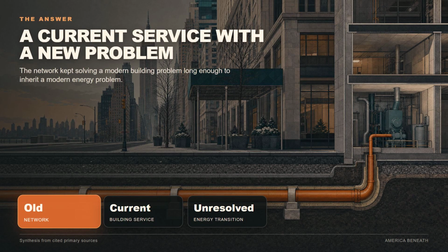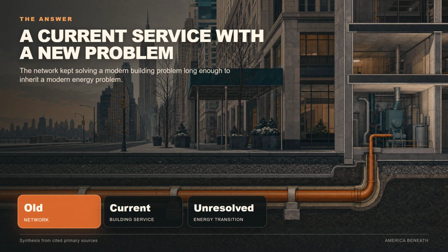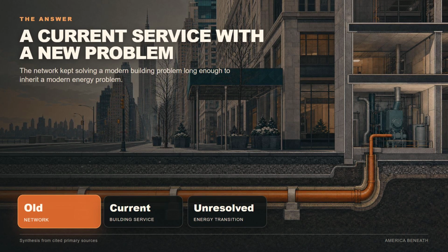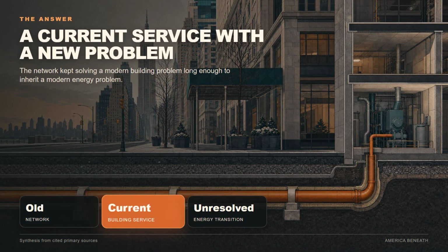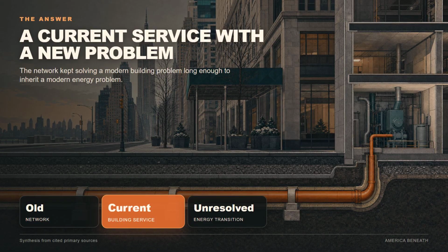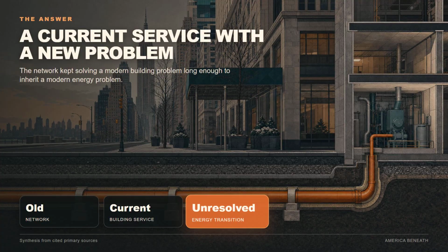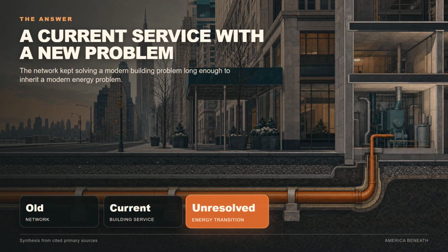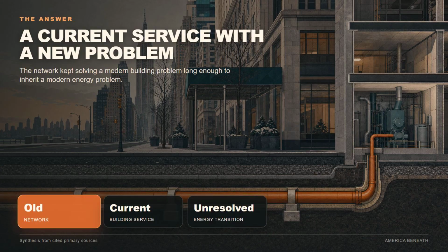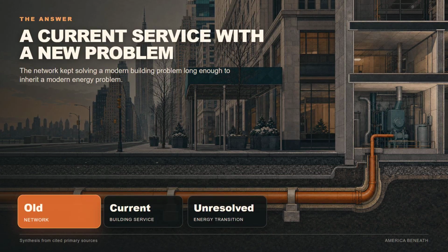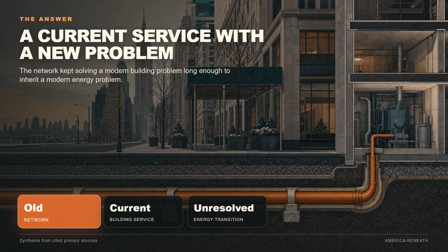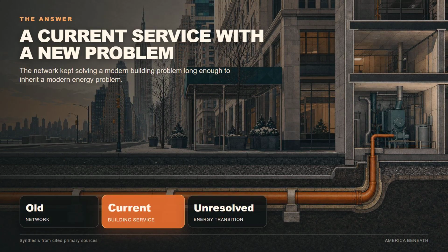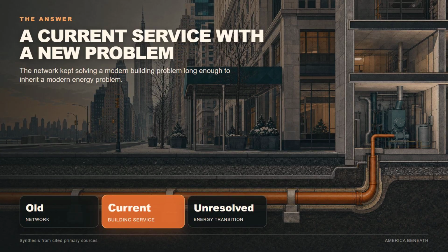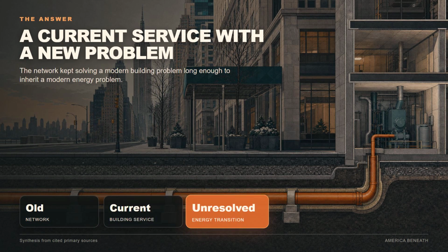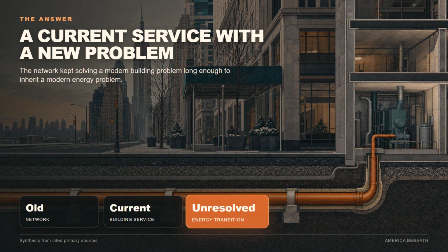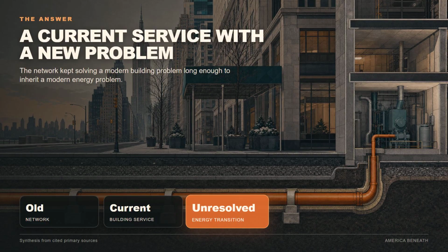So why does Manhattan still run on steam? First, the phrase describes an active utility in parts of the borough, not a museum piece, and not every building. Second, one connection can support several jobs, including heating, hot water, cooling, and specialized processes. Third, dense buildings may avoid some on-site production equipment, while replacement can require space, electrical work, and disruptive changes inside occupied properties. Those benefits will not be equal for every customer, but they explain why removing the network is not a simple modernization switch. The system's age made it familiar, its continuing usefulness kept it relevant, and its dependence on natural gas now prevents an easy environmental victory lap.